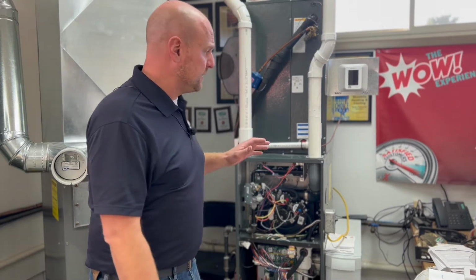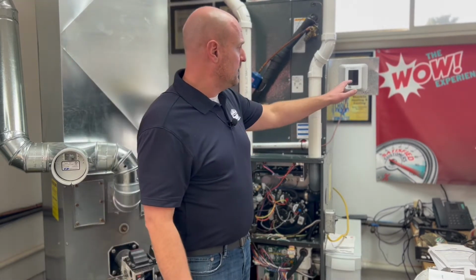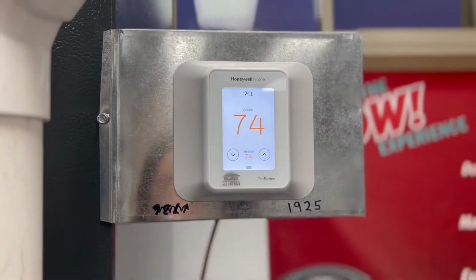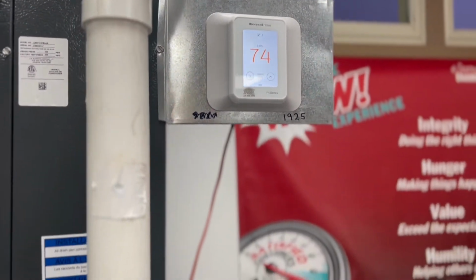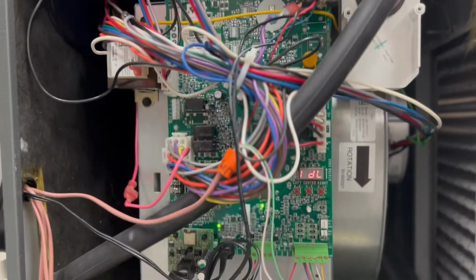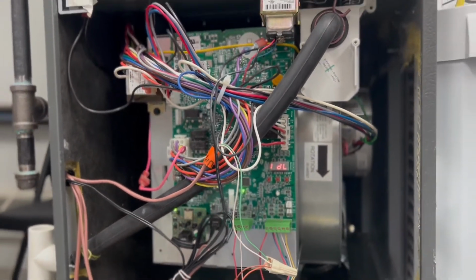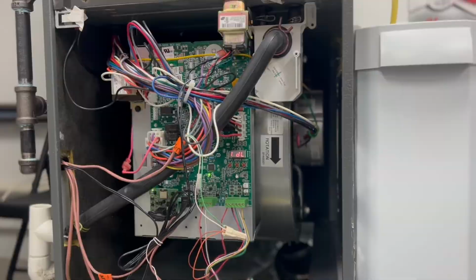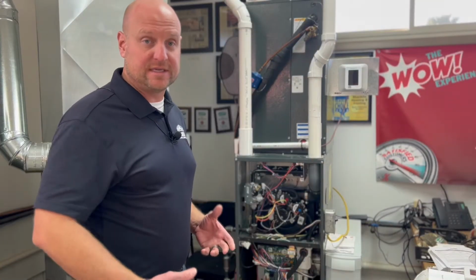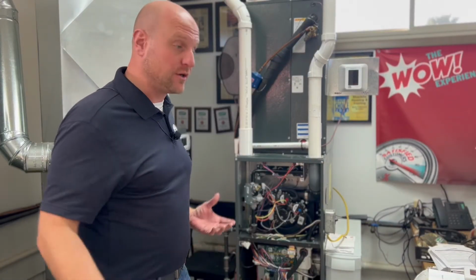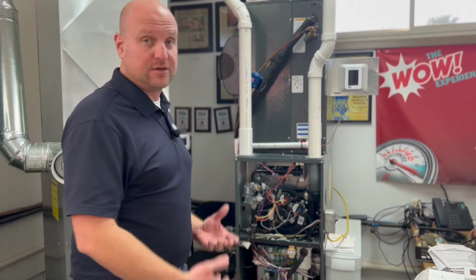The furnace itself is waiting for a call from the thermostat. So the circuit board will receive a 24-volt signal from the thermostat down to the circuit board on the W terminal. That's going to tell the furnace that, yes, we need heat, let's go ahead and turn on or start the process of heating your home.